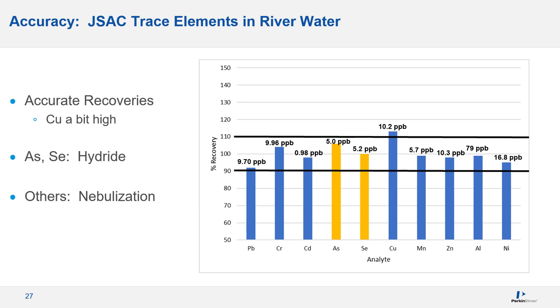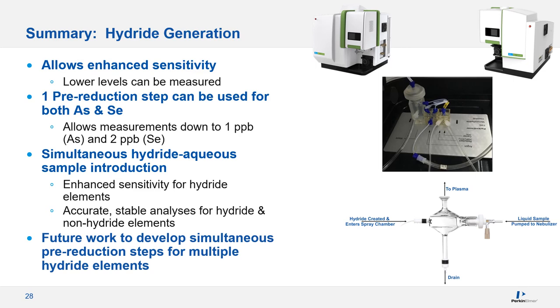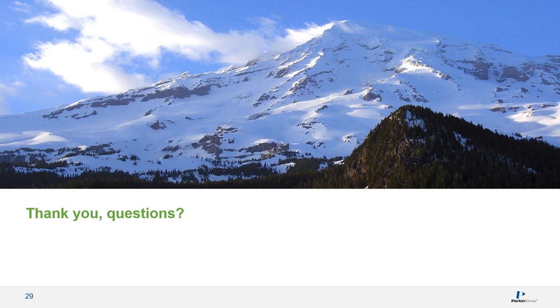In summary: hydride generation allows enhanced sensitivity for measuring lower levels. A single pre-reduction step can be used for both arsenic and selenium, enabling measurements down to 1 ppb for arsenic and 2 ppb for selenium. Using the Hydromist simultaneous hydride-aqueous sample introduction system, we see enhanced sensitivity for hydride elements similar to dedicated hydride analysis, while achieving accurate, stable results for non-hydride elements. Future work will develop simultaneous pre-reduction for additional hydride elements and further optimize Hydromist conditions.